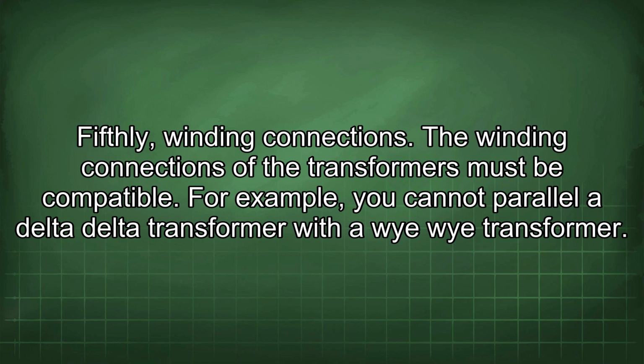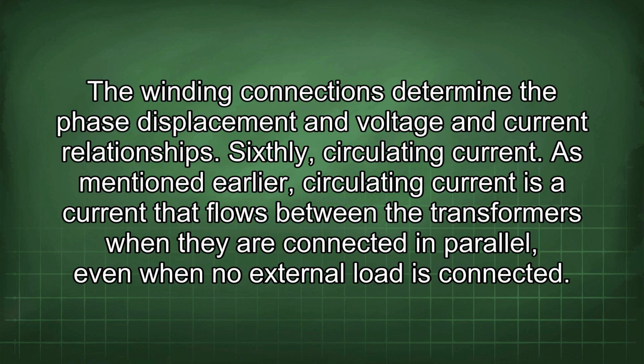Fifthly, winding connections. The winding connections of the transformers must be compatible. For example, you cannot parallel a delta-delta transformer with a Y-Y transformer. The winding connections determine the phase displacement and voltage and current relationships.